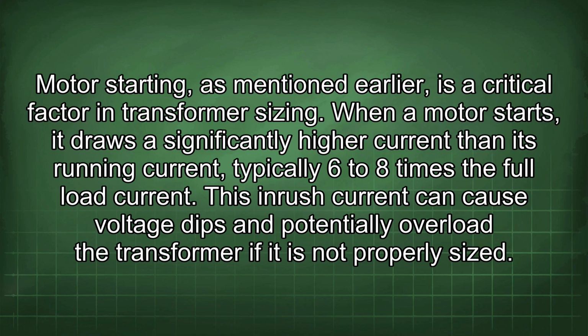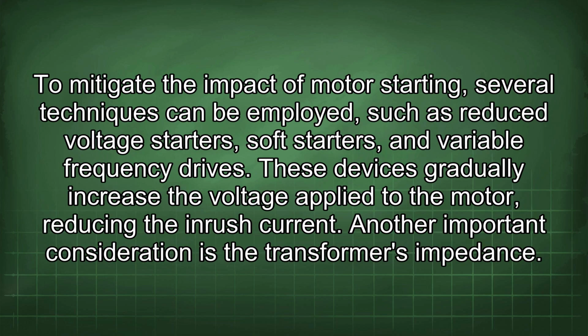Motor starting, as mentioned earlier, is a critical factor in transformer sizing. When a motor starts, it draws a significantly higher current than its running current, typically 6 to 8 times the full load current. This inrush current can cause voltage dips and potentially overload the transformer if it is not properly sized. To mitigate the impact of motor starting, several techniques can be employed, such as reduced voltage starters, soft starters, and variable frequency drives. These devices gradually increase the voltage applied to the motor, reducing the inrush current.